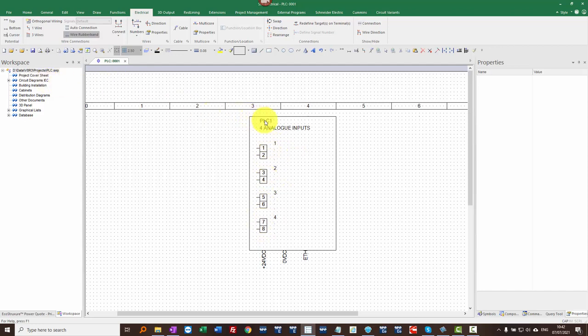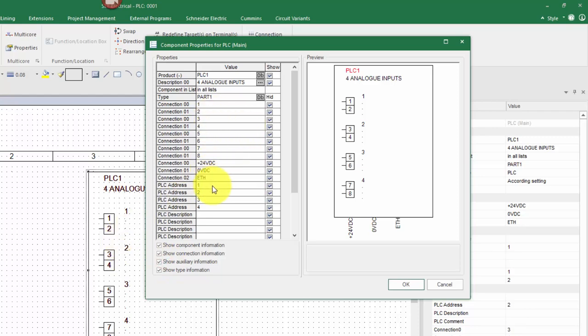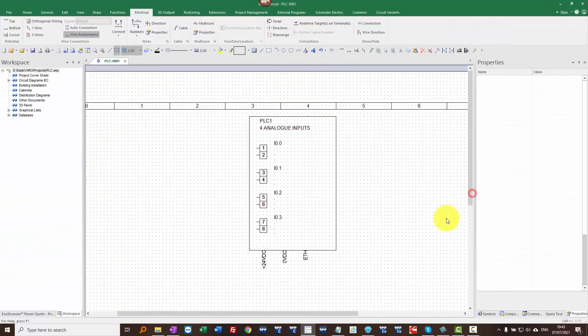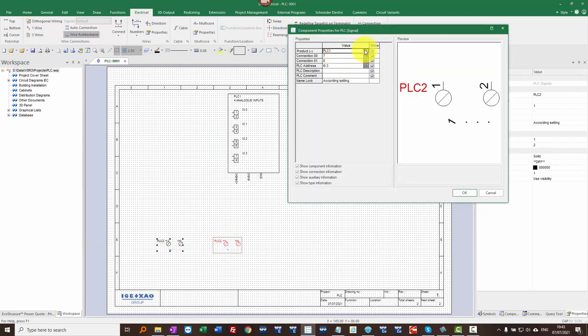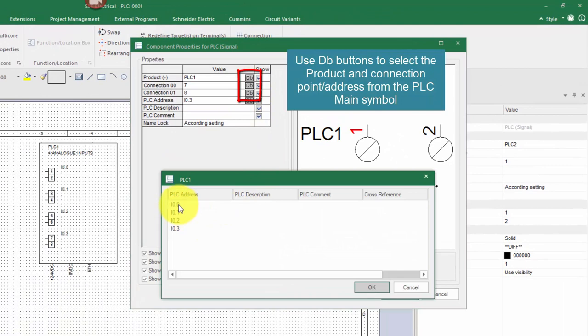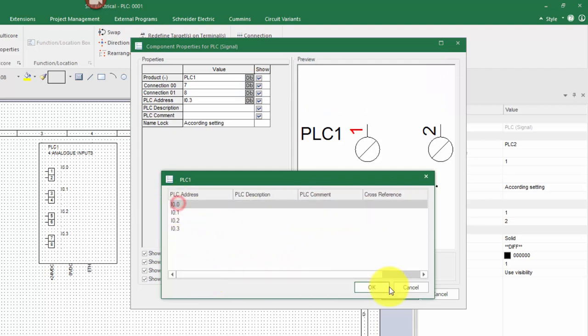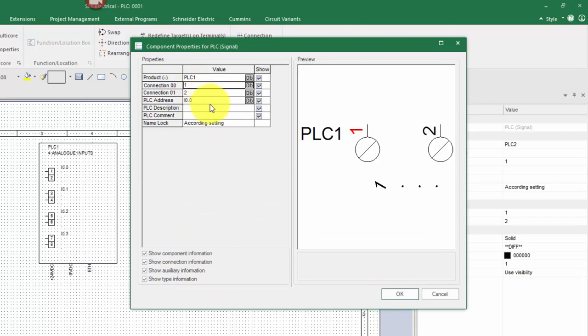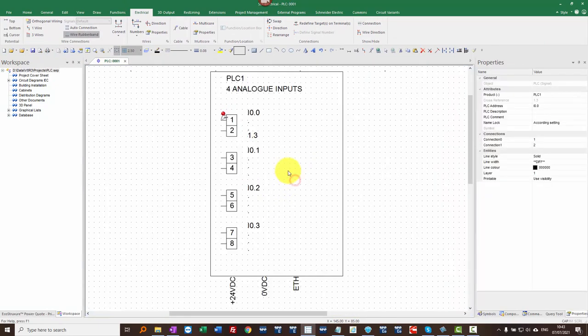Because I set up the properties, if I double-click on the card I can see all the information together. Show Auxiliary Information shows not just the connection points and descriptions for the main card, but all of the inner PLC signals. I'm going to go into the addressing and set this as I0.0, press Enter, and I can see it's automatically addressing the rest. I'm going to go down to my PLC signal, hold down Ctrl, copy it across to the right, and select two things: the PLC product and the connection. Notice it shows a list of addresses and on the right the connection points. If the cross reference is not filled in, that slot is free — you can select it, click OK, and it fills in the connection points, the address, and any descriptions or comments.